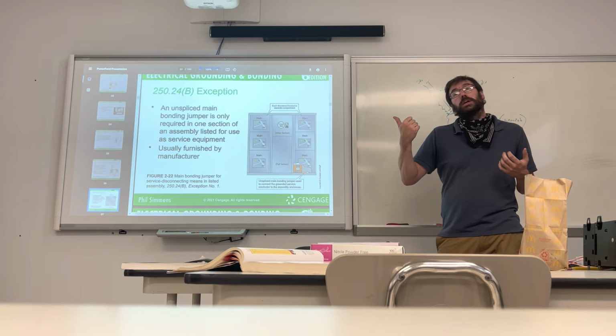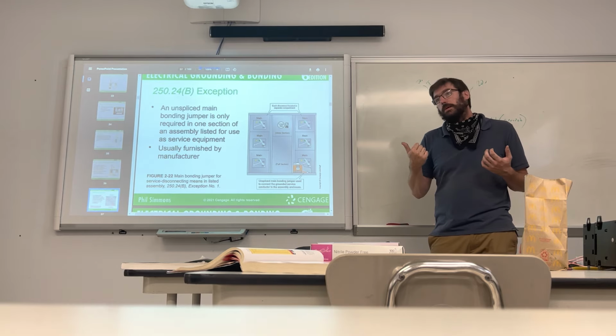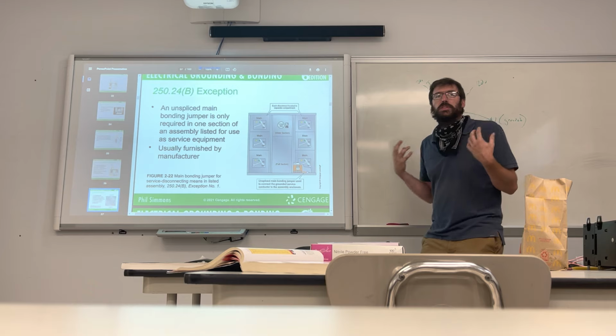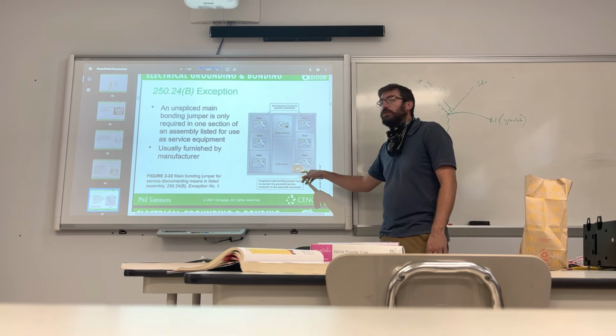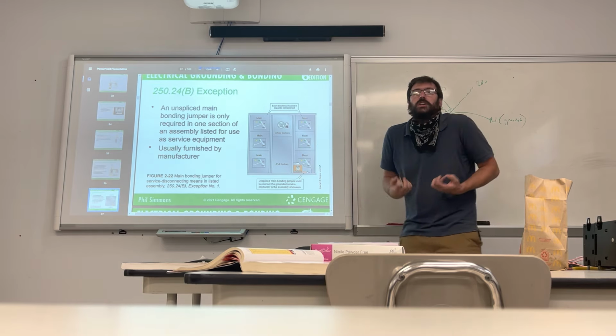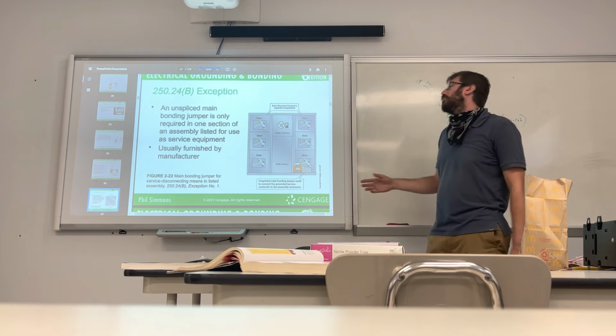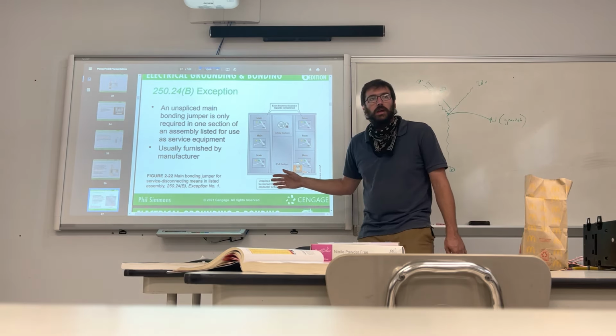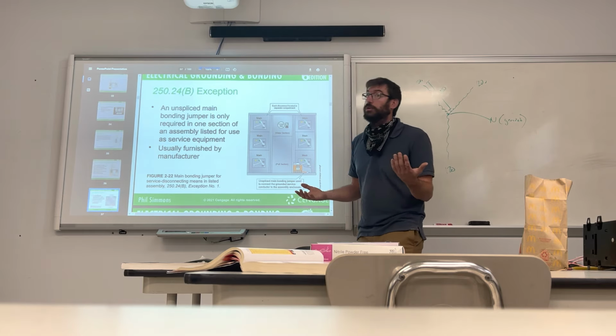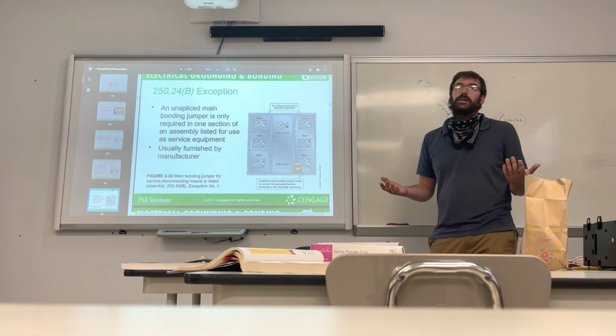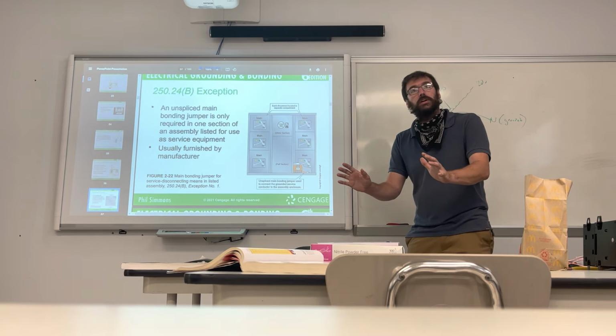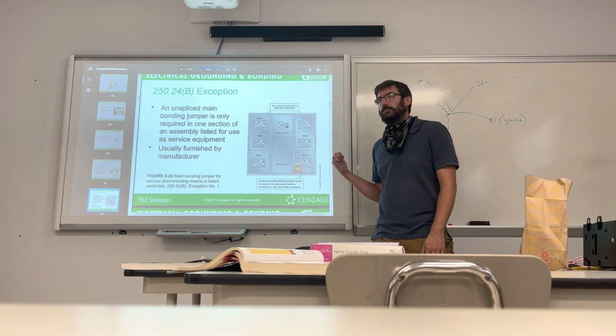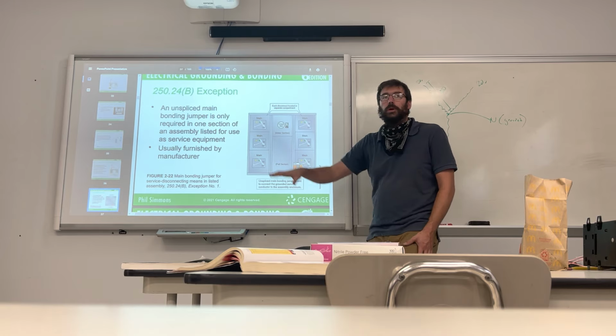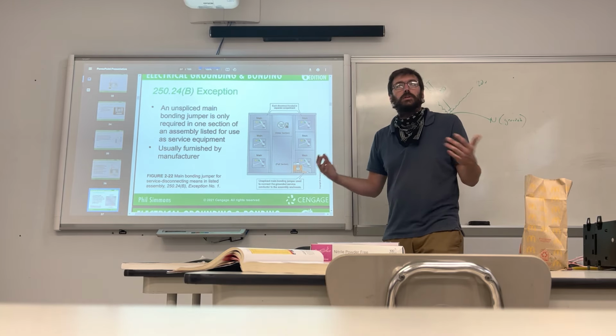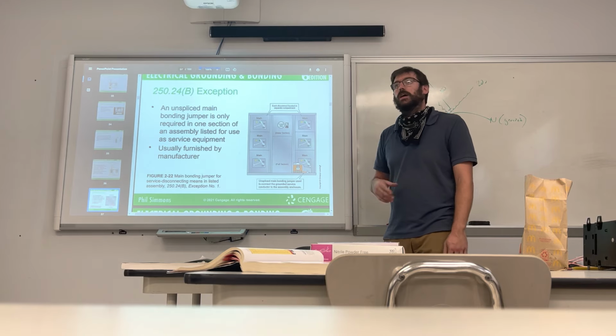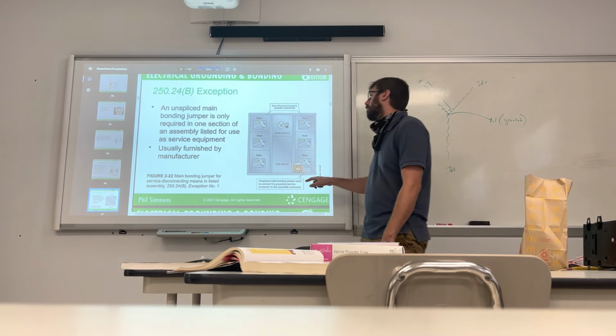Like look at the big green monster in the back of our shop. That thing's burly. And it's so thick and burly that if you ground one portion of it, it's pretty much grounded the entire thing just based on how strong and thick the steel is. And that's usually provided by the manufacturer. And anything made for electricity has to go through who? UL. So if it was manufactured and UL cleared it, then it's good to go for us. So there will be a lot of ground points that are put in by the manufacturer. Use them. Don't pretend like you're smarter than they are. Trust me, they're way smarter than we are. So, just so we know that.